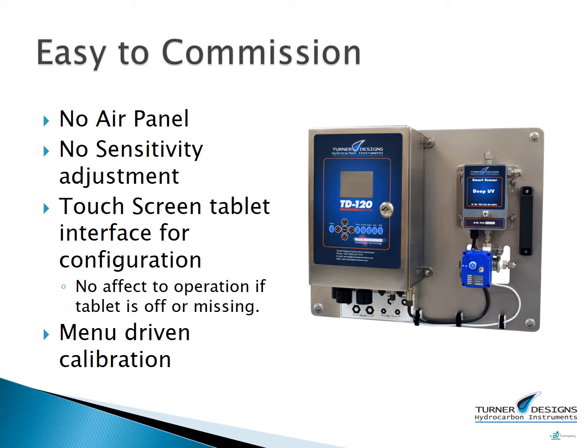Without the need to adjust an air panel or a sensitivity knob, the calibration and commissioning is a simple step-by-step menu-driven operation. Because the tablet is used only during the actual calibration and commissioning, the TD120 will operate normally should the tablet be missing or damaged.